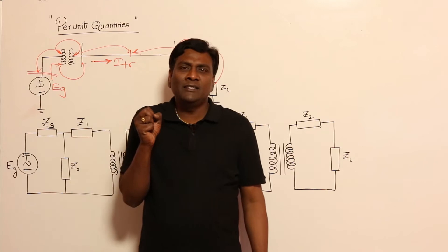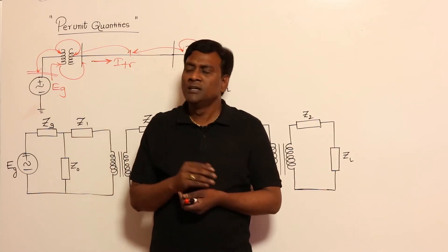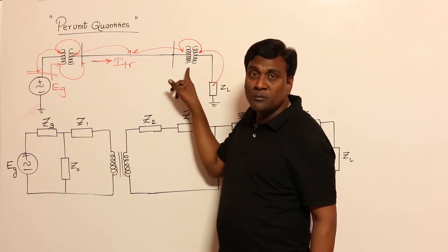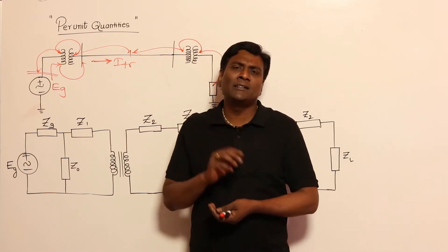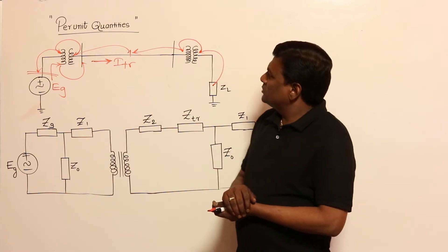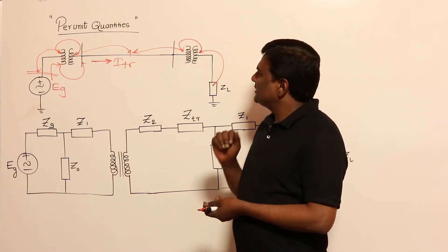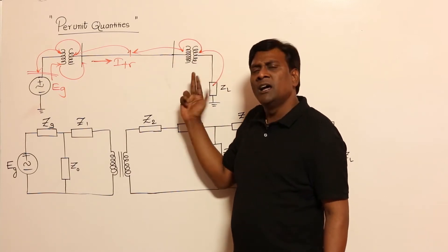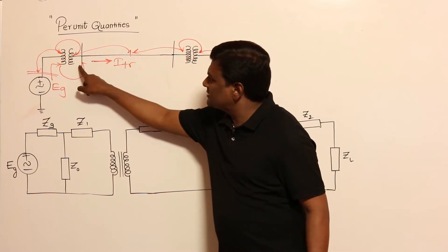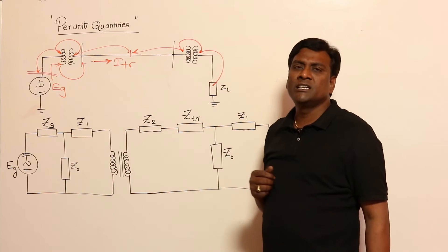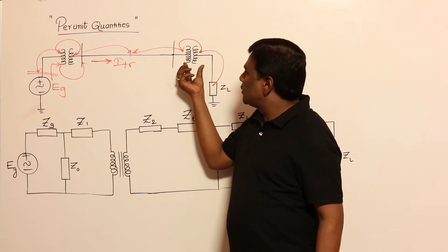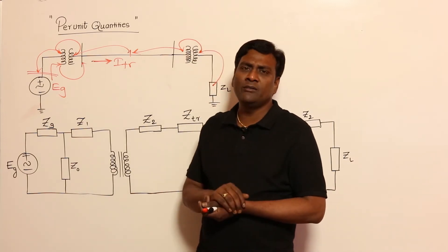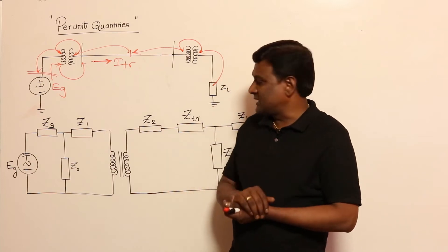The main difficulty here is the transformation ratios of the transformers. Without transformers the physical AC power system cannot exist, but because of transformers, analysis on paper becomes very complicated for load flow studies. Our purpose with per unit quantities is this: if we can eliminate the transformer not from the physical world, but on paper for analysis, then we can simply add all impedances directly without reflecting from LV to HV or HV to LV.